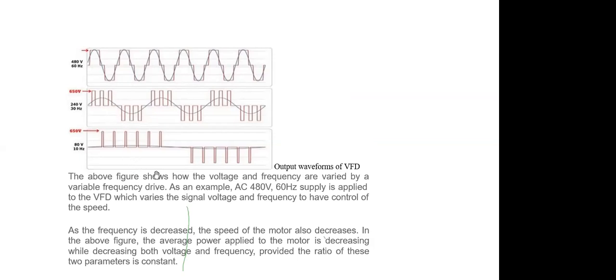converting to DC. Then, as we say here, the above figure shows how the voltage and frequency are varied by a variable frequency drive. As an example, AC 400 volts, 50 hertz is applied to the VFD, which varies the signal voltage and frequency to have control of the speed. This is after this conversion. I mean, these are the waveforms after the conversion. And with this waveform, this width is reduced and speed is controlled.